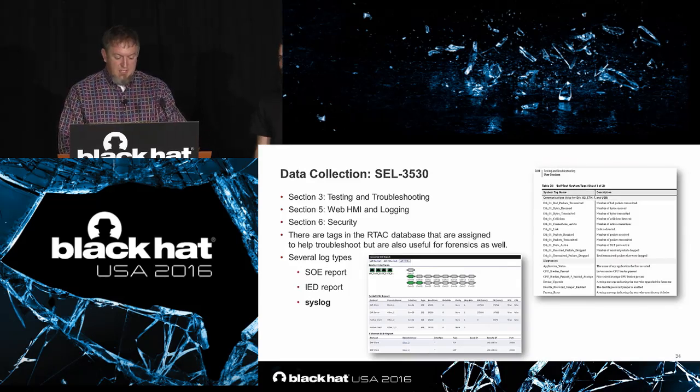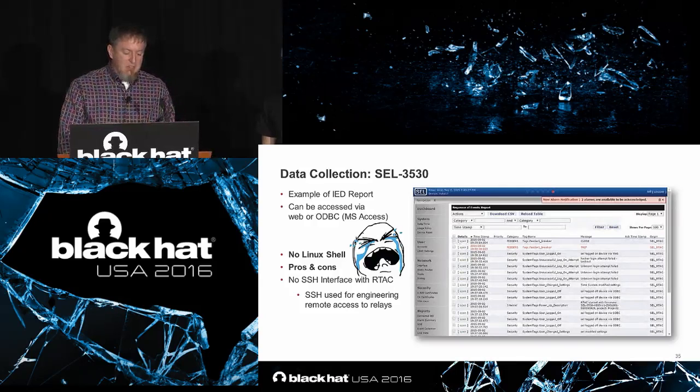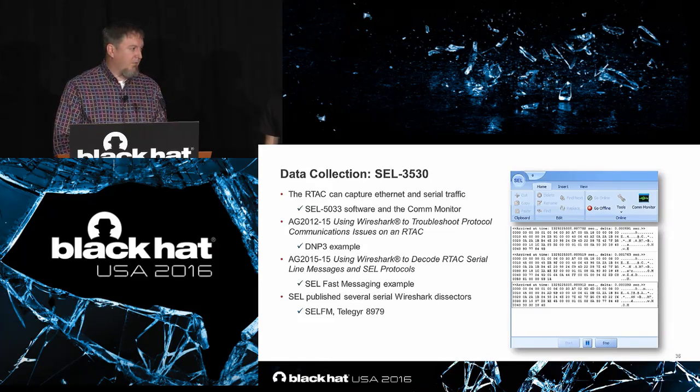Very interesting. You can see quickly which different ports are being used, like there's some troubleshooting points that it stores in the tag database, and you can also look at syslog. Here's an example of an IED, Intelligent Electronic Device report, and you can access this with ODBC. Unfortunately, there's no Linux shell, so there are pros and cons with that. So Schweitzer really locked this down, but we can still collect forensics data.